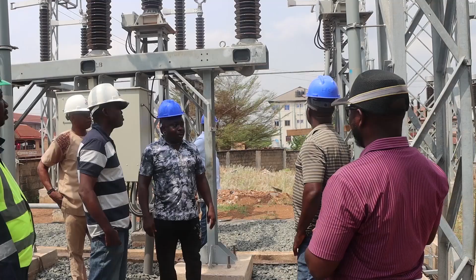Dr. Thomas Inugonum, General Manager Transmission of the Enugu region of TCN, who led the commissioning, stated that TCN has approved the procurement of a new 60 MVA power transformer to replace a decommissioned leaking unit. This will add 48 megawatts to the substation's capacity upon completion.